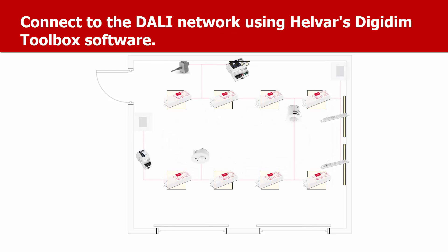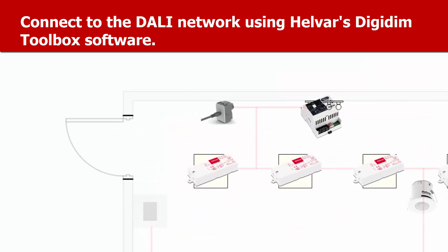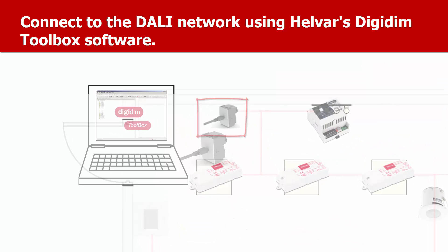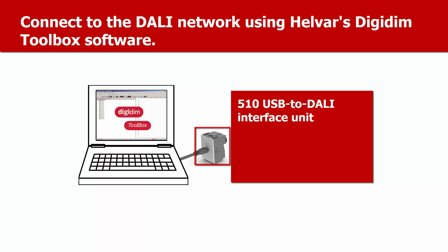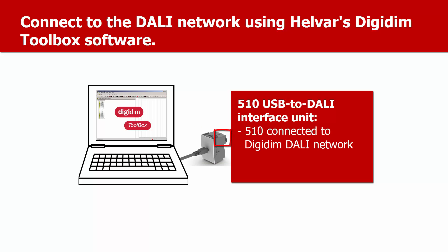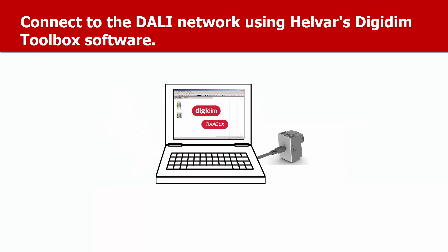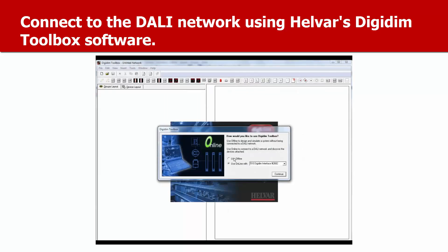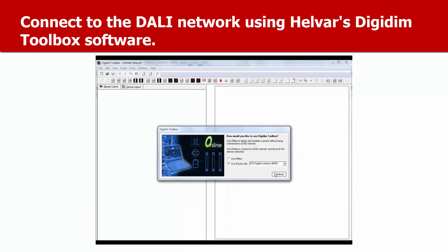What we're going to demonstrate now is connecting to the DALI network using Helvar's Digidim Toolbox software on a Windows PC, and using Toolbox to configure the lighting controls. Note that you can still make some adjustments to the lighting scenes even without the PC. We're going to use a Helvar 510 USB to DALI interface to connect our PC to the DALI network, but other interfaces are available. Connect the PC via USB cable to the interface. Open the Toolbox software, select the 510 interface, and click Continue.